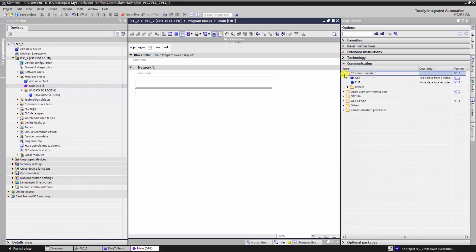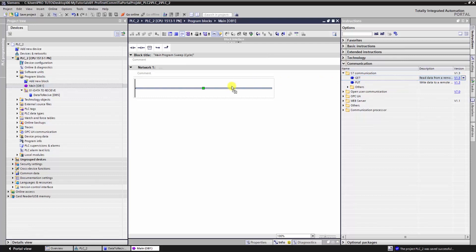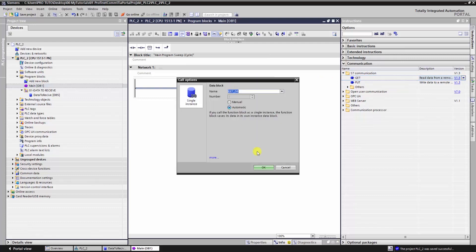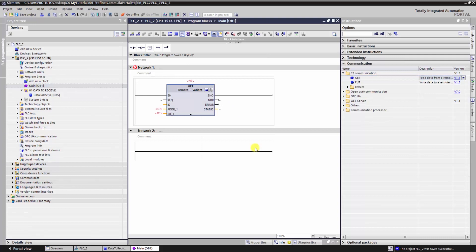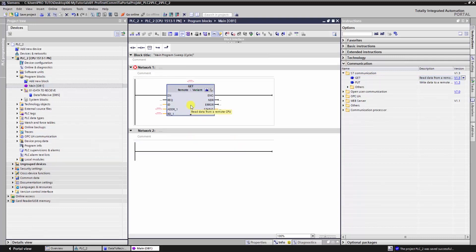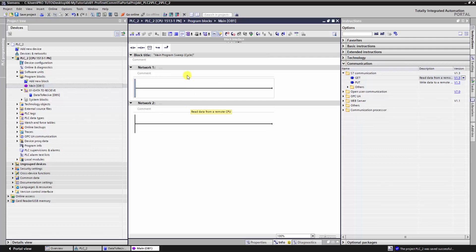A lot of people get confused here. They think they should add a GET block here in the second PLC, so it's wrong. You have the choice to choose either PUT or GET to send data between the CPUs, but not both, so pay attention.